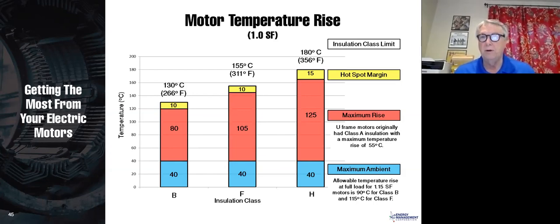Now, Class H, a lot of motors, in fact, most motors have some Class H materials in them, but if you want to have a motor that's actually stamped and nameplated with Class H insulation, that's going to be a significant premium, and I don't see any point in doing it in most applications. Now, if you have applications in which the motor is in a furnace or something where it's really hot, then yes. But typically, you don't want to run motors that hot. Even if the winding insulation can handle it, you're probably going to have bearing and other problems.